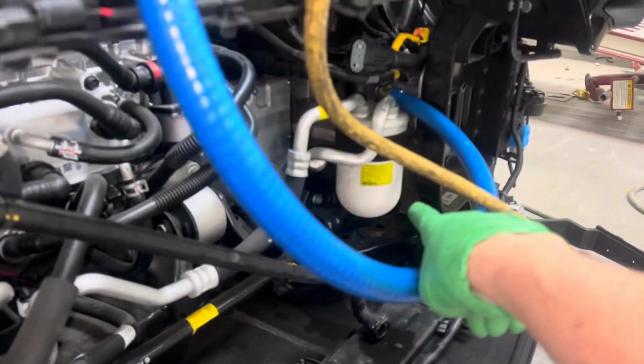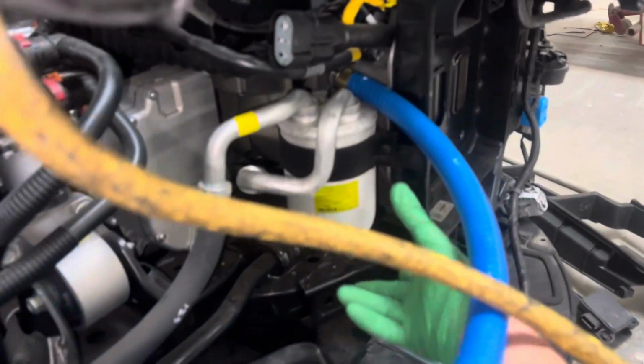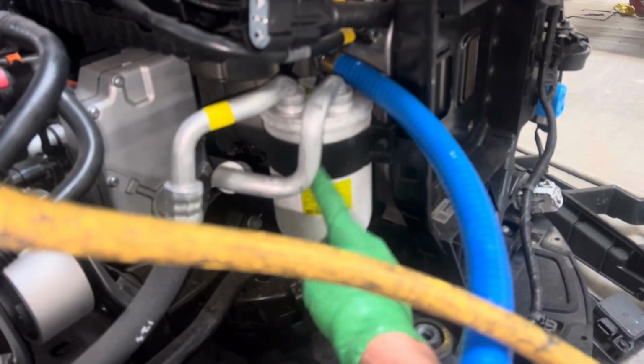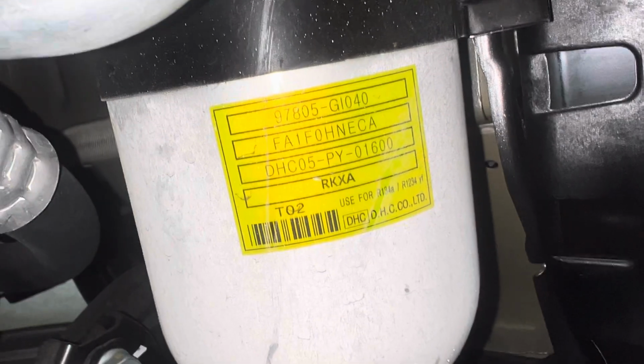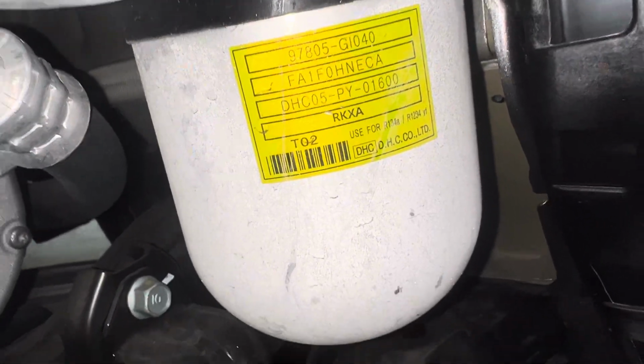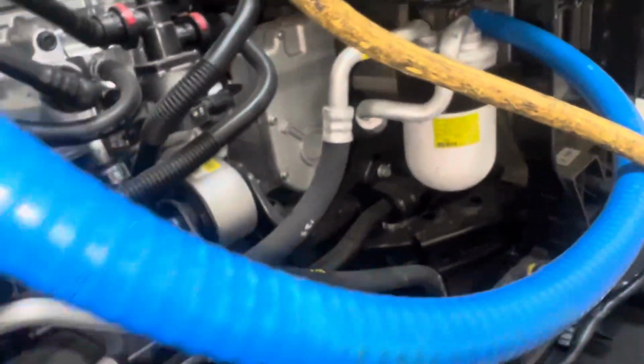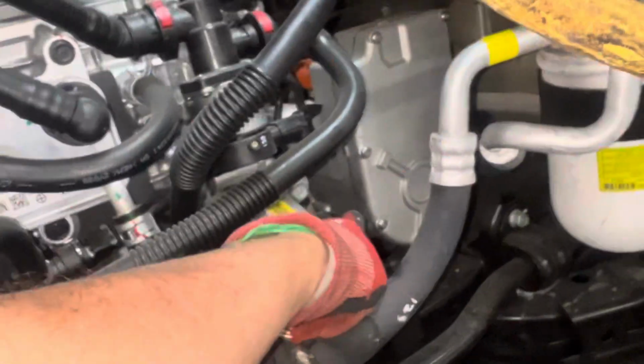You see that frozen bottle down there? This is filled with refrigerant right here. This is your accumulator, you see that? If you want to look up some part numbers and try to get some prices, let's see if I can get you a price. It's all icy, I'm recovering the refrigerant. So there's your part numbers, if you want to look up prices, go right at it. Here's your compressor, the inverter is built in the back. That is your high voltage 3-phase compressor.